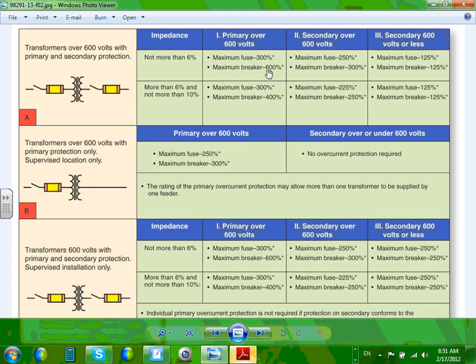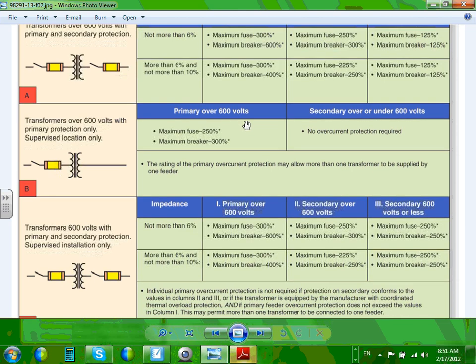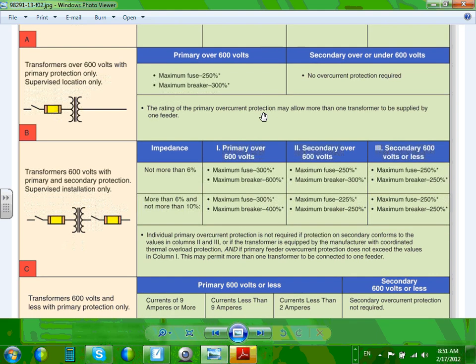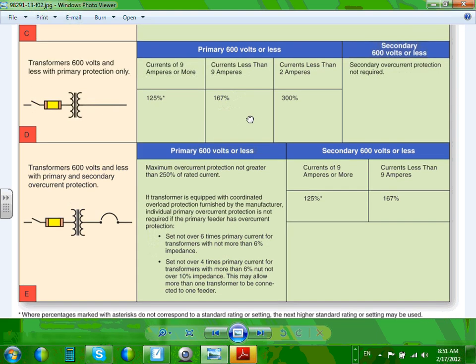They size them based on a bunch of things from the table. If the impedance is less than 6%, overcurrent device, if it's fused 300, if it's circuit breaker 600, and the same thing for 300, 400, secondary overcurrent device 600 over 600. Here's how we do it. If it's under 600, this is how they do it: 125% of the full load current of the transformer. Then you go to primary over 600, secondary over or under 600, and in different locations. So this table, as I said, I will go over more of it as we go to the industrial. I'm just going to flash it.